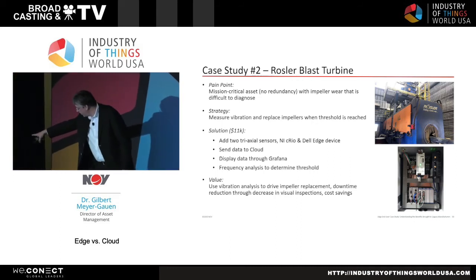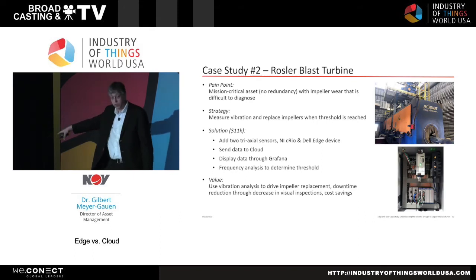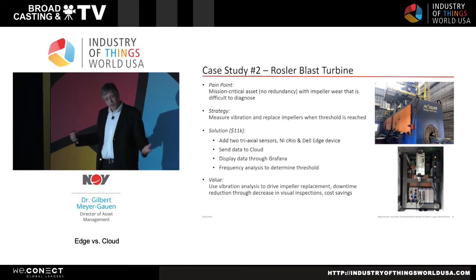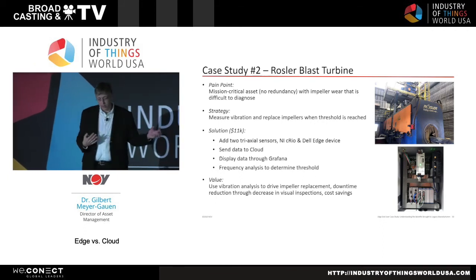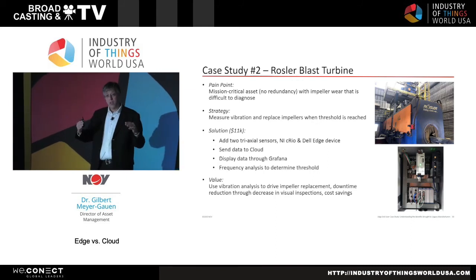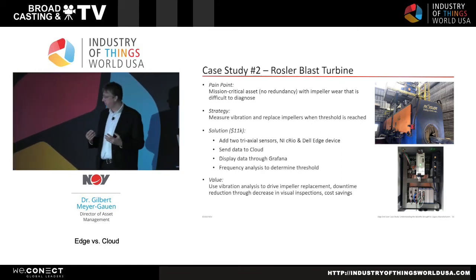So down there at the very bottom, that's the data acquisition device. It's from National Instruments. It's called CRIO and costs $5 grand, that thing alone. Vibration data, again, you need a lot more bus speed, a lot more horsepower to handle this analog wavelengths data. I mean, we are talking about 20,000 readings per second per axis, you know?